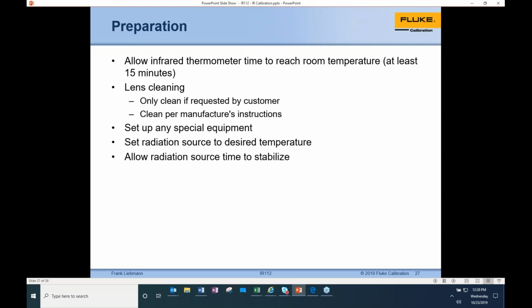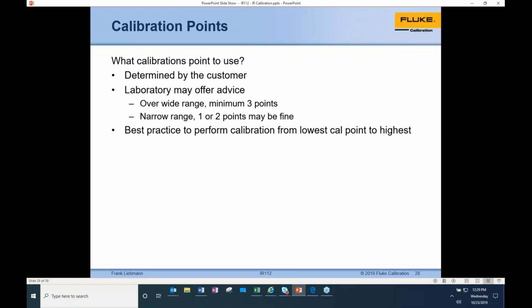So the setup, any special equipment, okay, we've touched on that several times, going with your distance, your size upward, partitions, maybe a purge. Once you get all that going, then the next piece is simple. The actual measurement is the easy part of this process. You're going to set the black body to your desired temperature. You're going to allow it to come up to temp and stabilize, and then you're going to simply take your readings. The good thing with our 4180 units is they do have a built-in alarm. You set your stability limit into that, and then it'll come up to temp, and when it's ready, it will beep at you and let you know, hey, I'm ready to be used now.